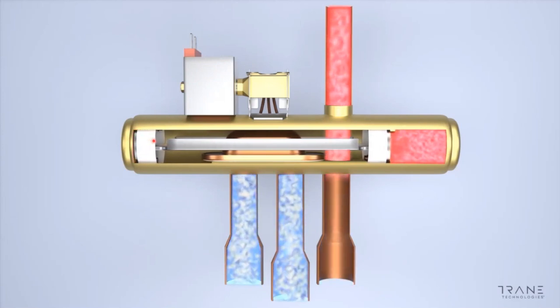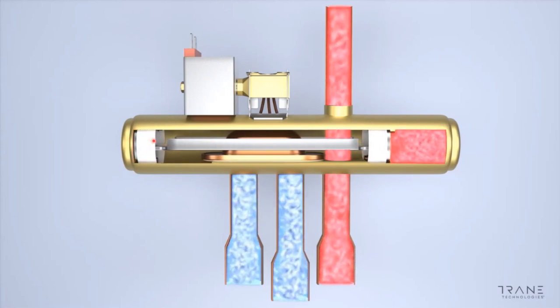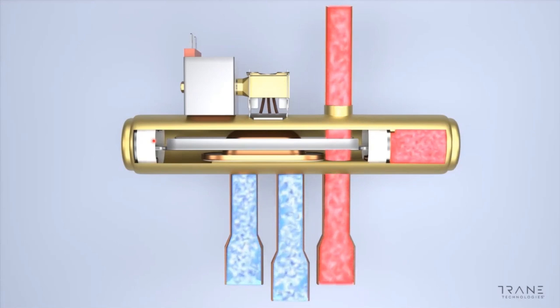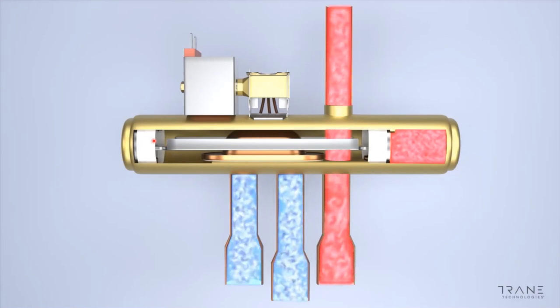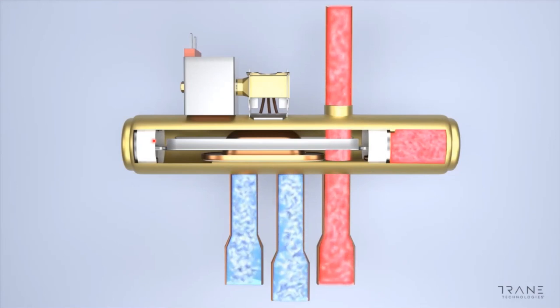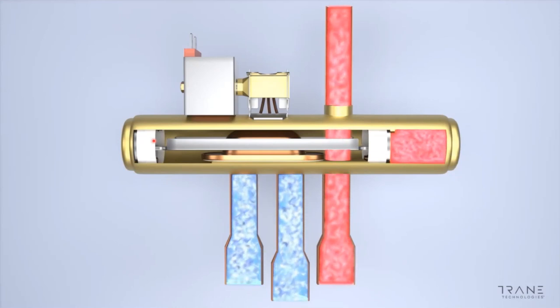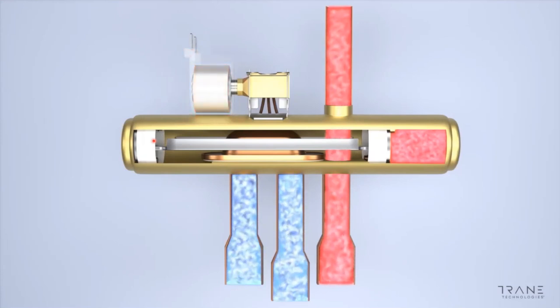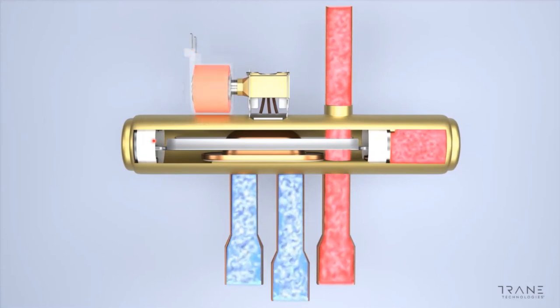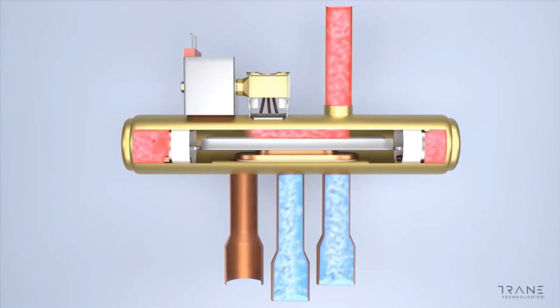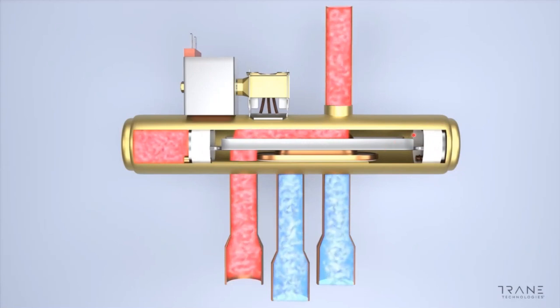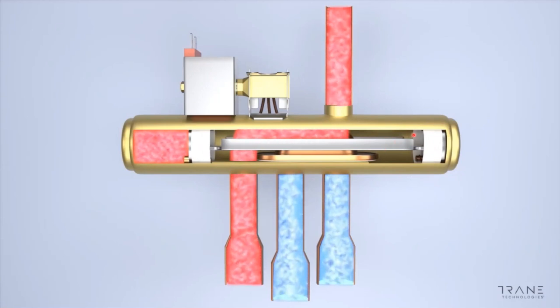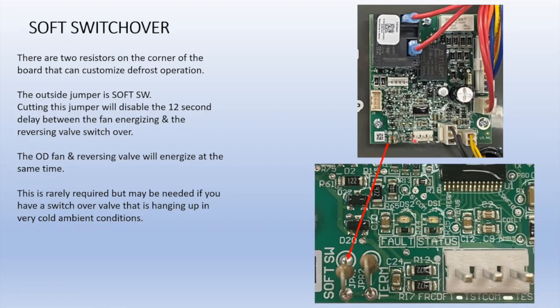So we talked about the outdoor fan turns on for 12 seconds to reduce head pressure before the switchover valve is disengaged. So if you do have switchover valves sticking in cold temperatures, getting stuck part way after a defrost, that's where you would cut that soft switchover so that it disengages the reversing valve when there's that high delta T. So as shown earlier, this is the jumper you would cut for that, and it would remove that 12-second delay from the fan coming on to the switchover valve.